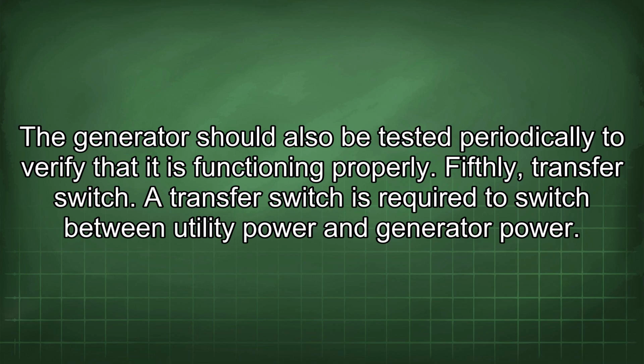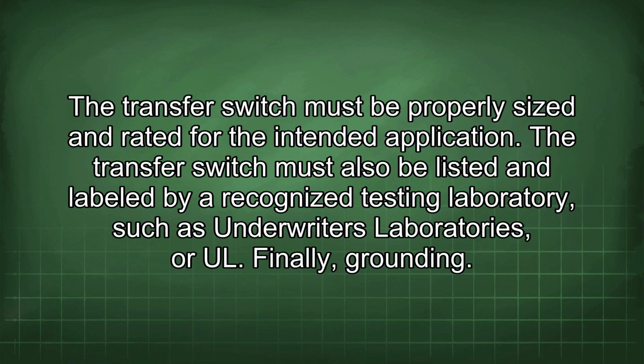Fifthly, transfer switch. A transfer switch is required to switch between utility power and generator power. The transfer switch must be properly sized and rated for the intended application. The transfer switch must also be listed and labeled by a recognized testing laboratory, such as Underwriters Laboratories or UL.